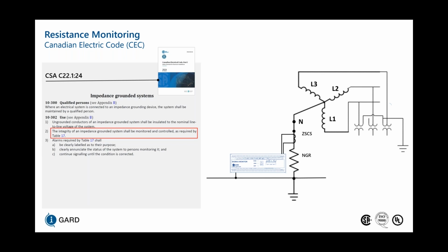So in the Canadian Electrical Code, it also states that the integrity of an impedance grounded system shall be monitored and controlled as required by Table 17, which we already went through. And that allowed us to modify our approach in terms of monitoring resistances to include a high frequency AC injection method through our sensing resistor.